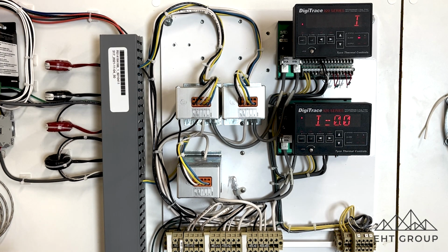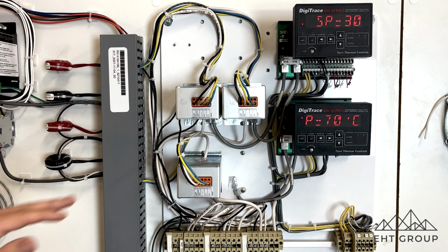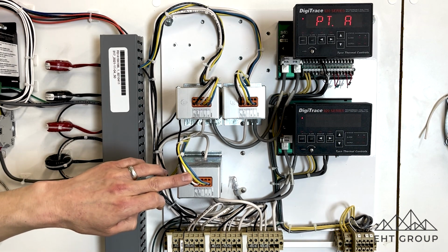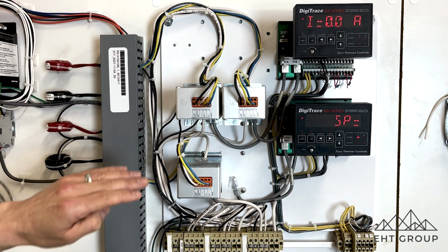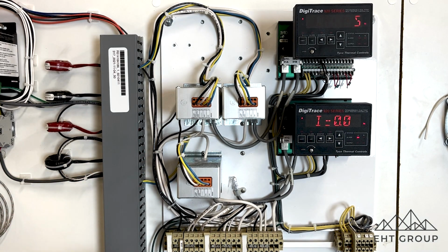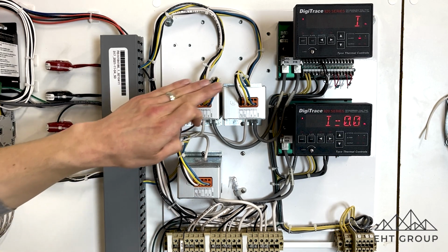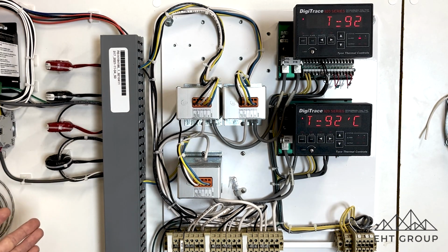Now, one thing I want to point out is that in older heat trace control panels, what we oftentimes see is that the control power will be paralleled from circuit 1A's supply voltage. It'll take our 120 volts, or 100 to 277 volts, and parallel it between all of the CT modules within a panel. And this is typically in older panels.